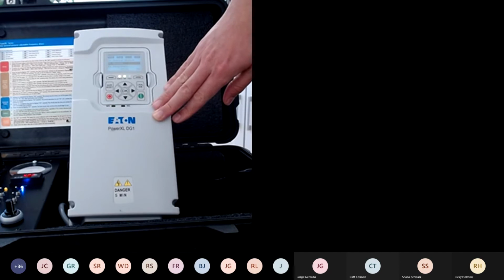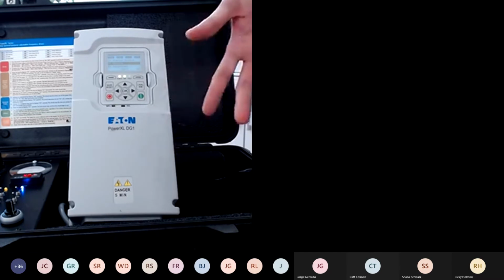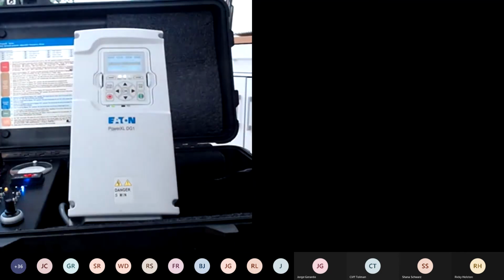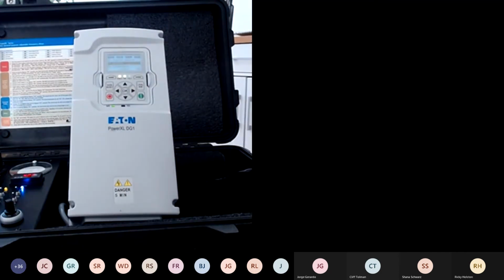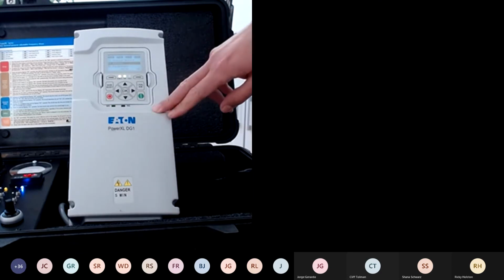Let's move on to the VFD. And again, live drive through remote signal, adjusting the speed. You do have your LCD displays here, so you can monitor the frequency, monitor the current, and you have a multi-monitoring application from the drive itself, where you can look at parameters. And let's see if we can review some of these parameters.